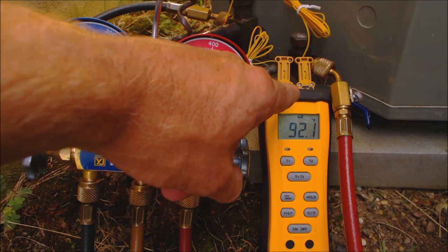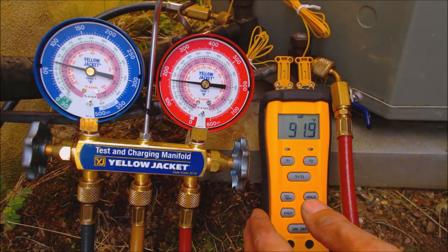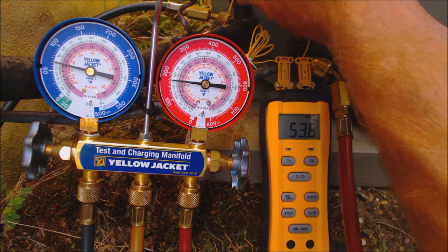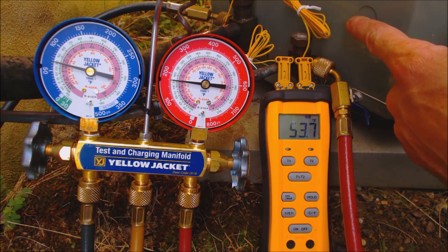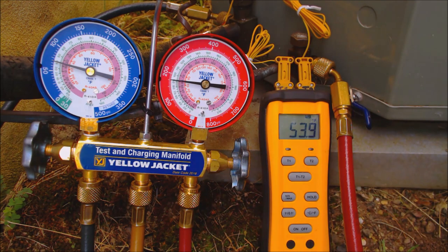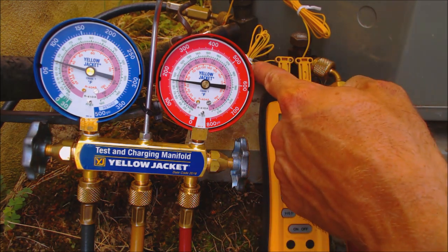We have the Fieldpiece ST4 temp reader. T2 is the suction line — the large line coming back to the compressor. The small line is where the refrigerant is in a complete subcooled liquid state, heading towards the metering device inside the house. We're going to pay attention to this liquid line.